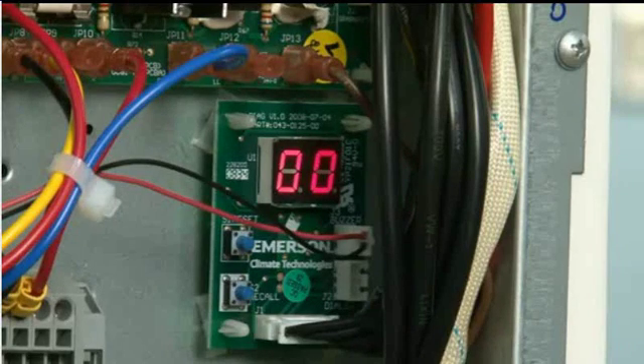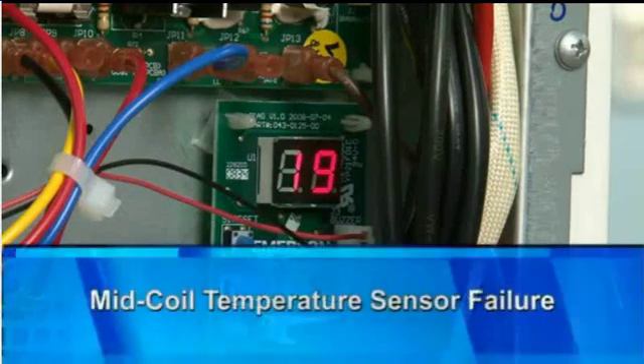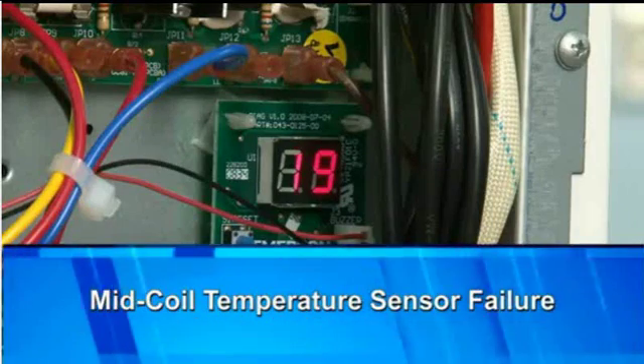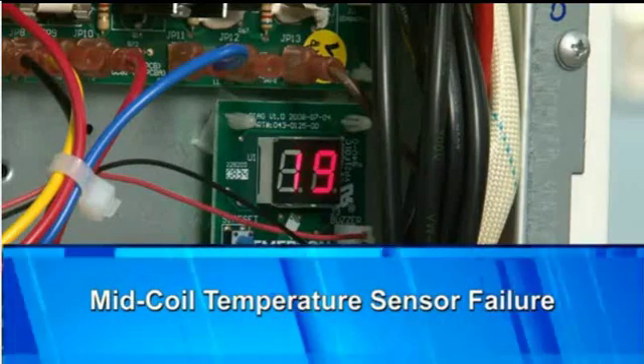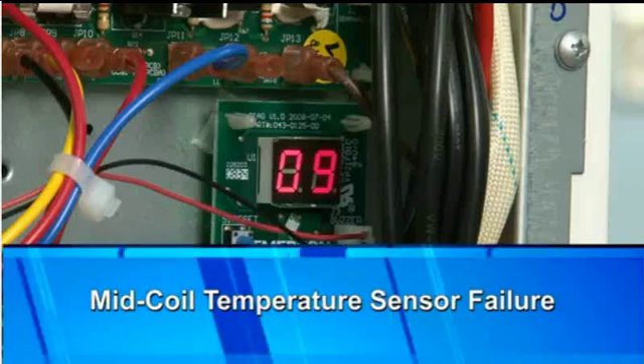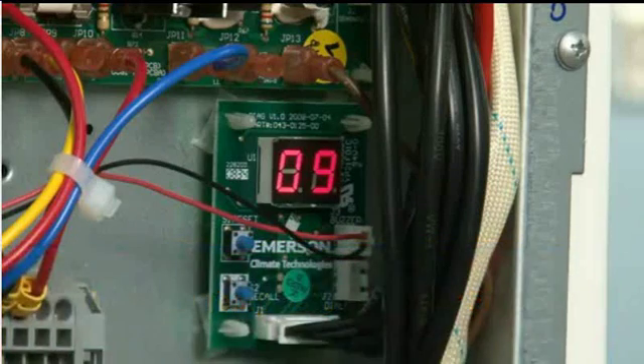Another example of an error code and the resulting fix is a mid-coil temperature sensor failure. Error 19 when the compressor is on, and error 09 when the compressor is off. To troubleshoot this error, we need to remove the sensor and replace it with a new one.